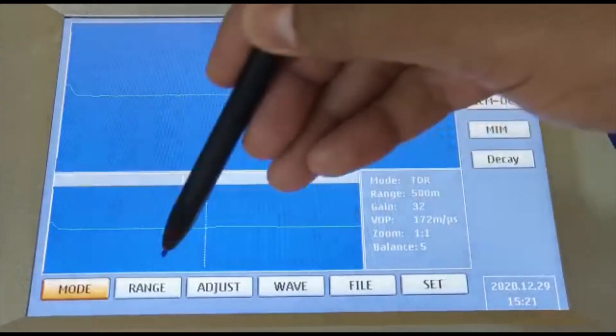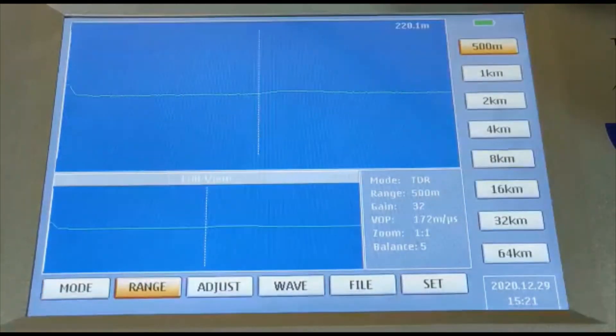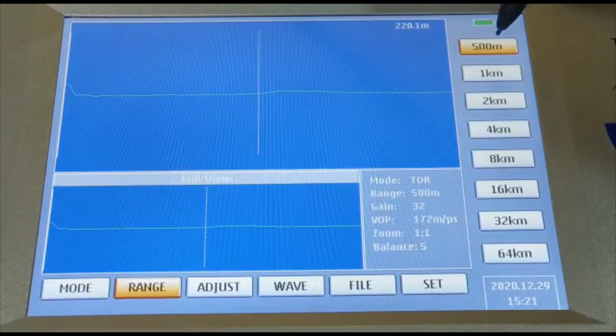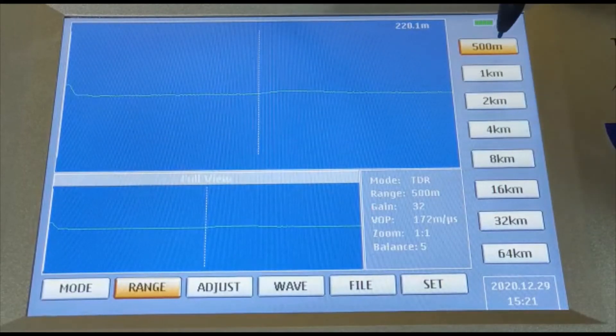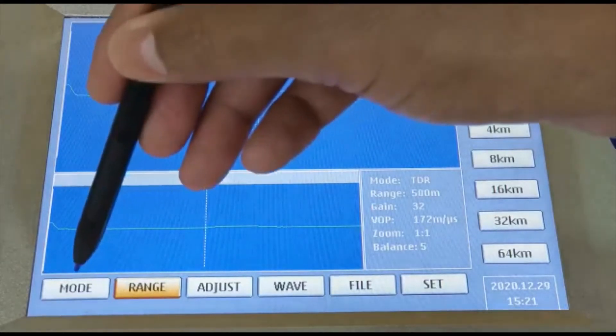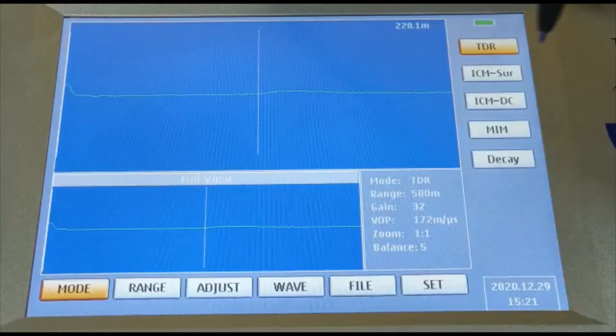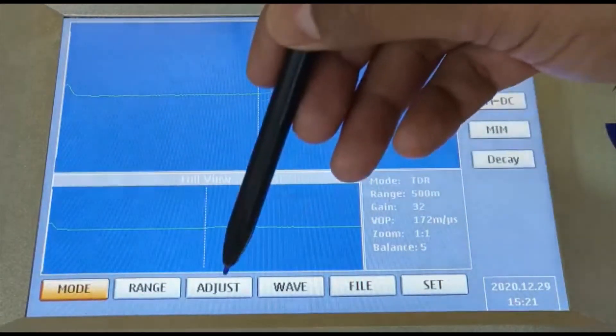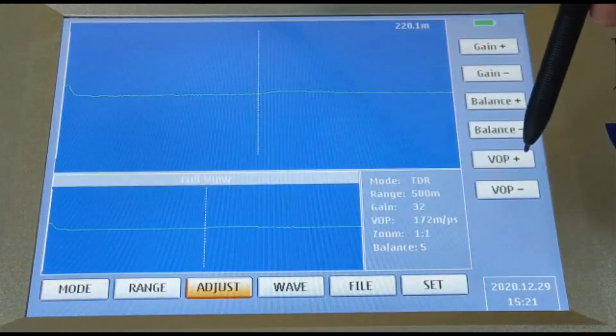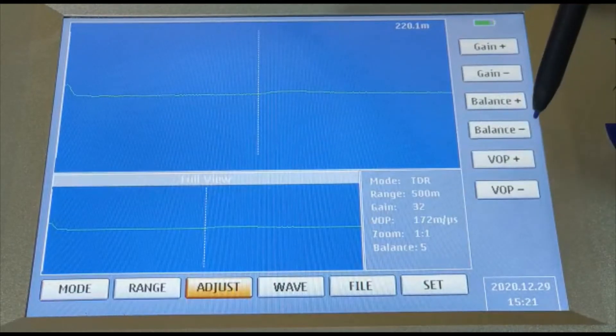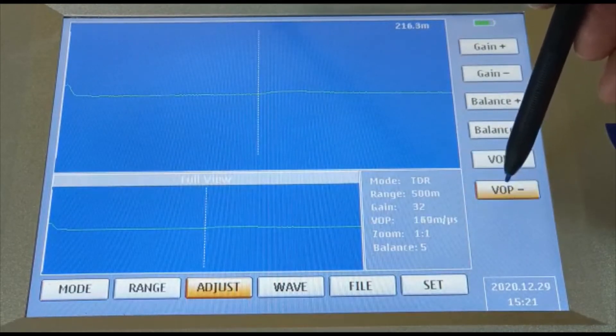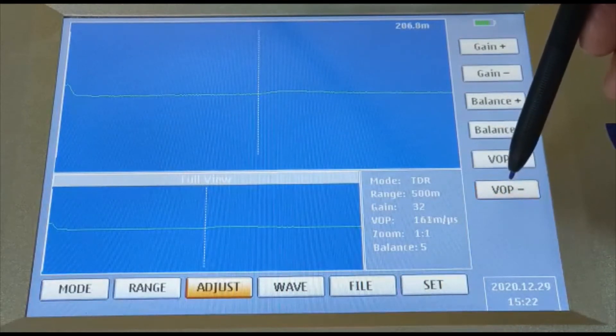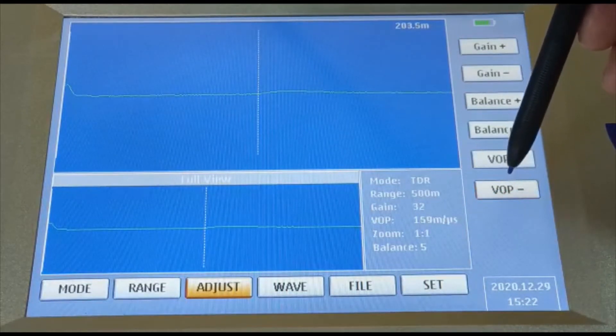Based on your cable distance or total cable length, select a different range. My cable length is 200 meters, so I keep the range at 500 meters with mode set to TDR. I will adjust my VOP based on the insulation of the cable so that I get an accurate location and accurate distance of the cable.